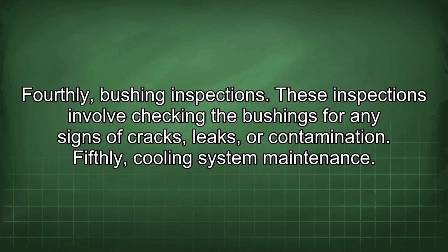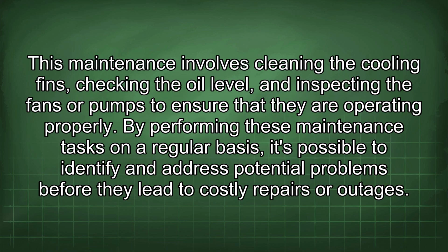Fourthly, bushing inspections. These inspections involve checking the bushings for any signs of cracks, leaks, or contamination. Fifthly, cooling system maintenance. This maintenance involves cleaning the cooling fins, checking the oil level, and inspecting the fans or pumps to ensure that they are operating properly. By performing these maintenance tasks on a regular basis, it's possible to identify and address potential problems before they lead to costly repairs or outages.